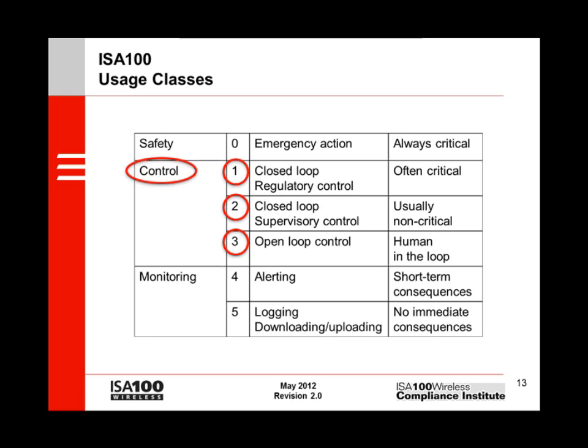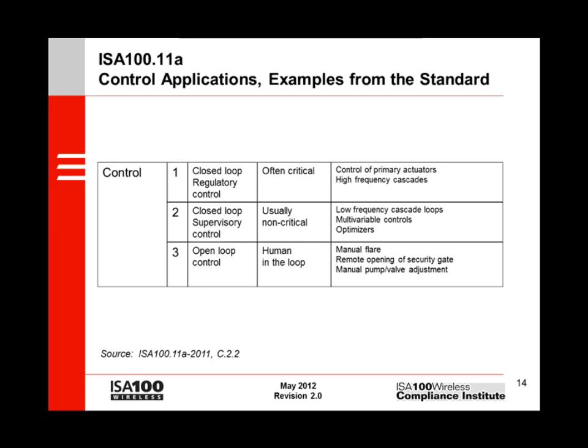Class 1 is closed-loop regulatory controls. Class 2 is closed-loop supervisory controls. And class 3 is open-loop controls. This slide summarizes the control application examples that you can find described in the ISA100.11a standard itself. Let's start with control class 3. The open-loop control examples in the standard all involve the user in the loop. An operator manually initiates a flare and watches the flare. A guard remotely opens the security gate. An operator performs a manual pump or valve adjustment.